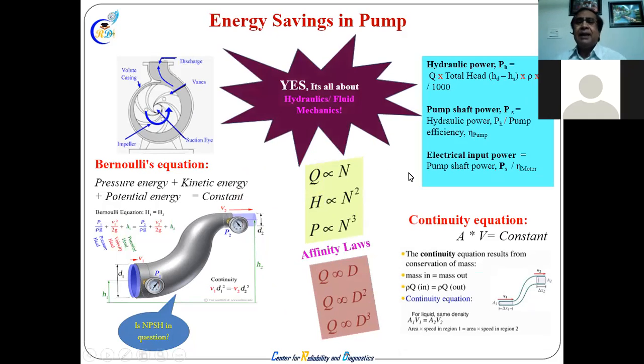So energy saving, yes, it is all about hydraulics and fluid mechanics. Energy saving is not just purchasing some energy product or purchasing some VFD product and putting it in, and then you save. No. Even if you put in the VFD, if people are not taking care of these things in operation, they will never get savings. And people will curse you. What happened? I'm not getting the savings. I purchased all this. I've changed to a VFD. Why am I not getting this?